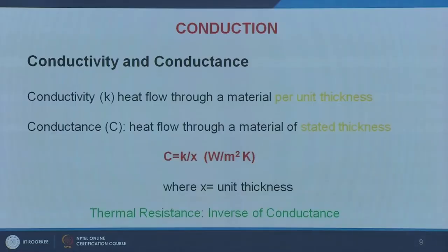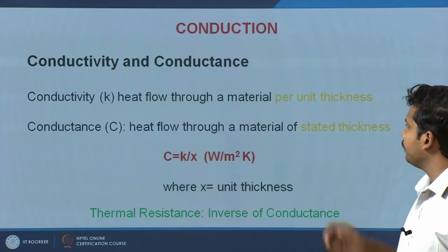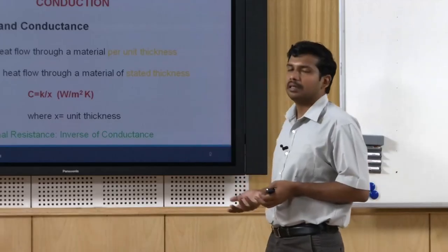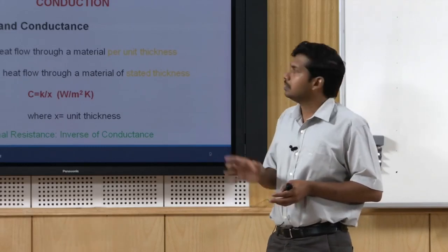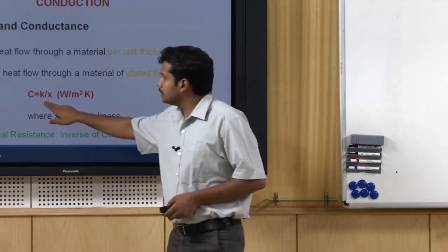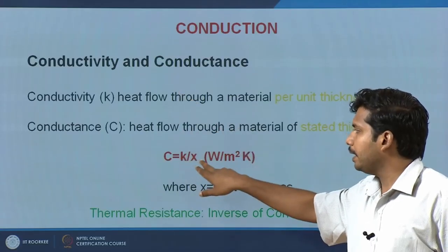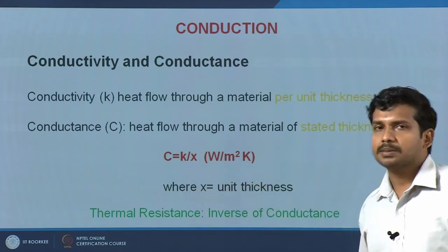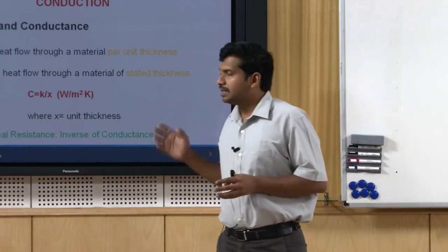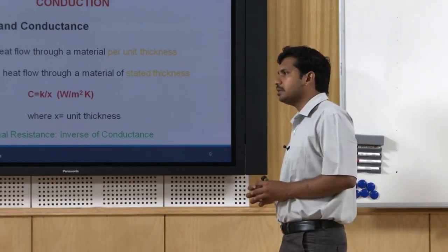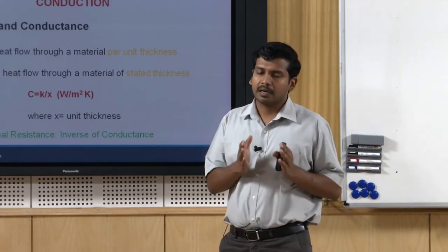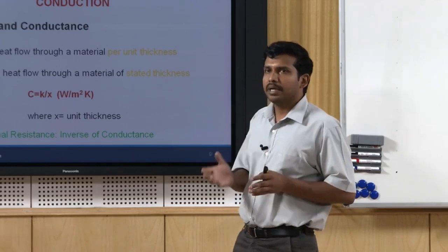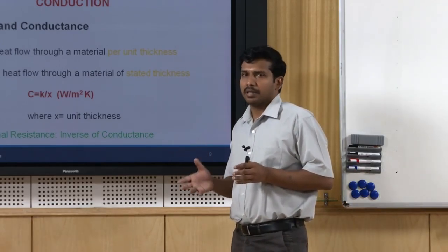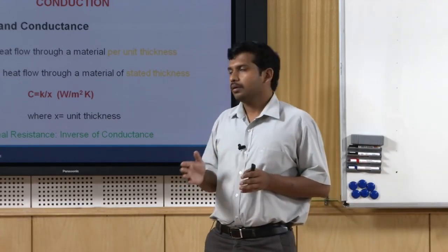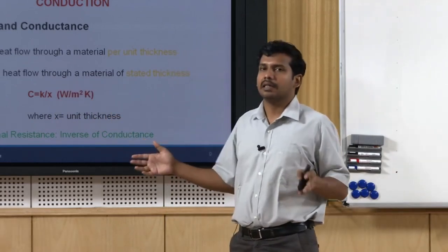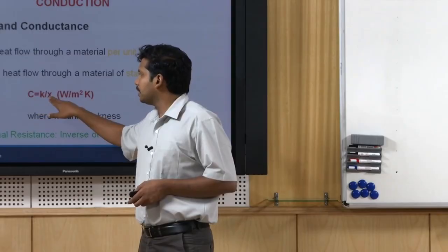The next important parameter is conductance. This is the heat flow through a material for a stated thickness. Now, we are starting to include the cross-sectional thickness of the particular material. So, this is conductivity K divided by X, where X is the thickness. The unit is watts per meter square Kelvin. For example, when somebody gives the conductance of a material, the first thing you should ask is for what thickness. Conductance for a 100 mm or 110 mm thick brick wall would be different from a 220 or 230 mm thick brick wall, because conductance includes a factor of thickness. As the material gets thicker and thicker, the conductance value is going to come down because thickness is in the denominator.